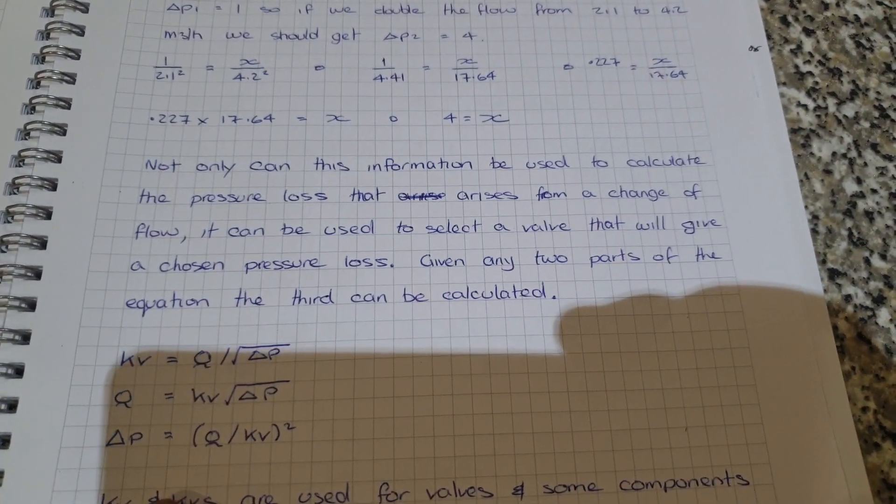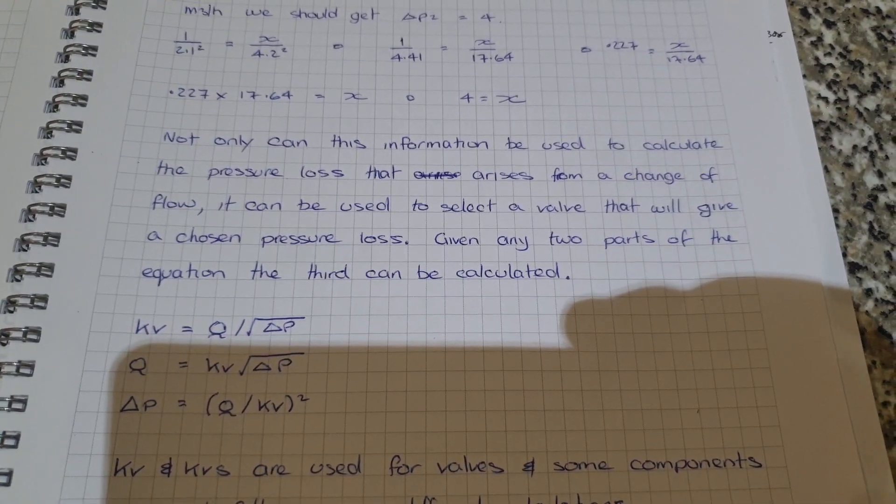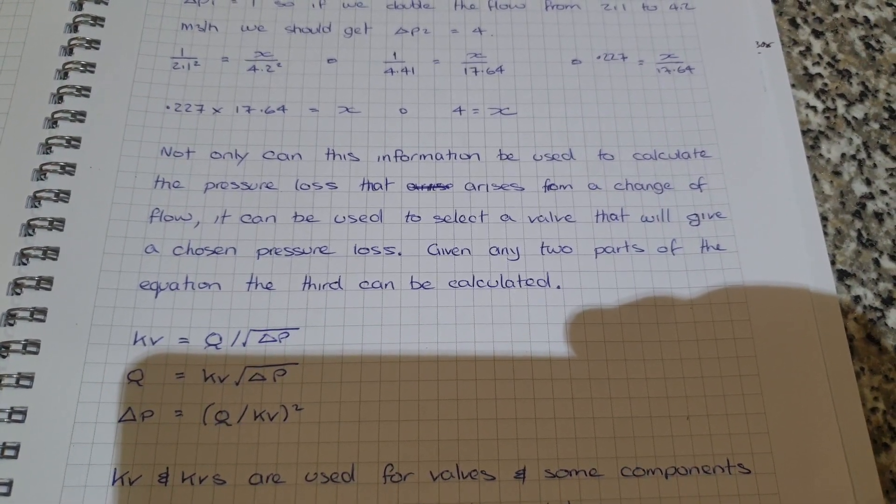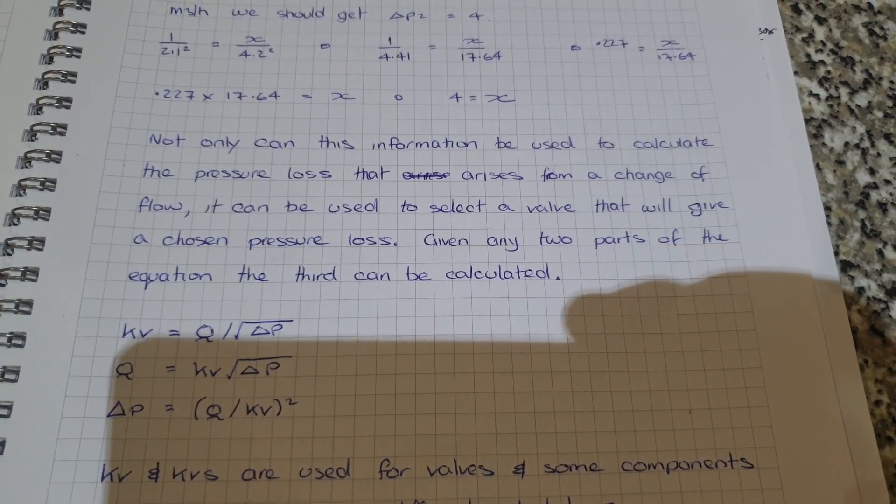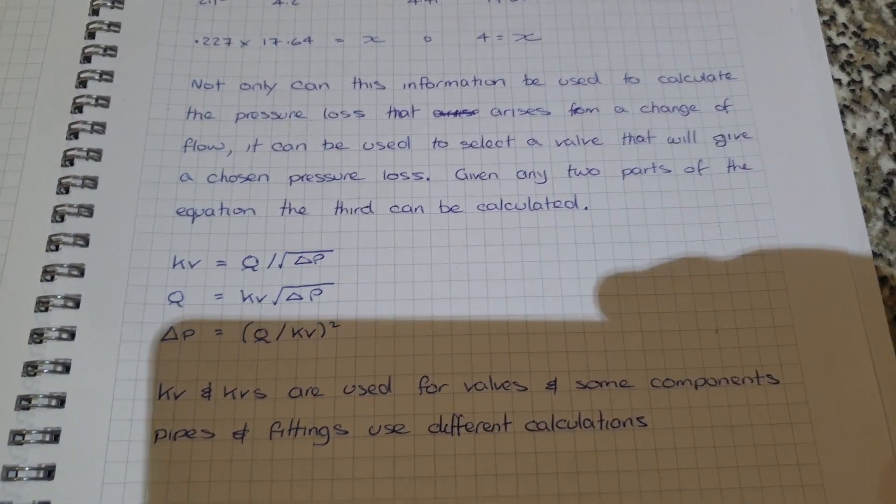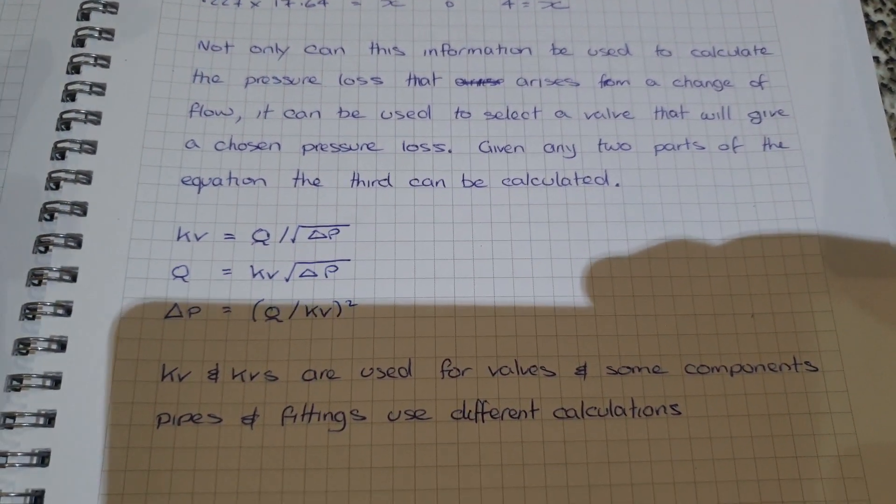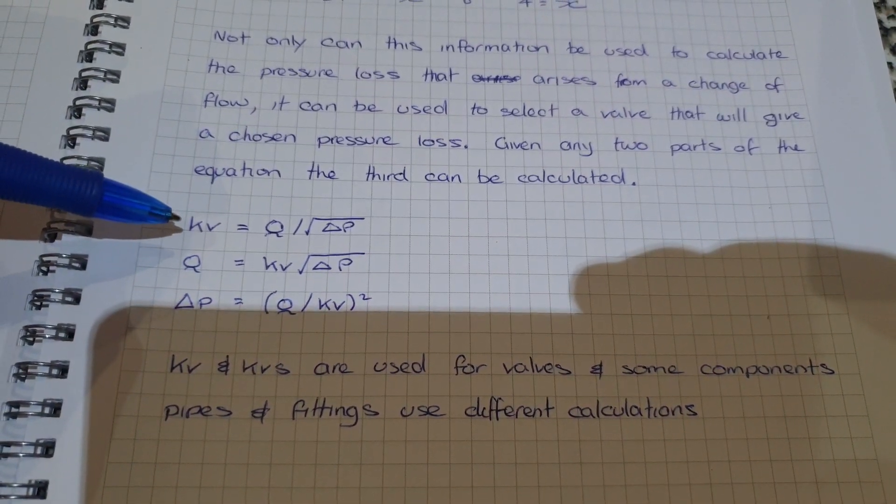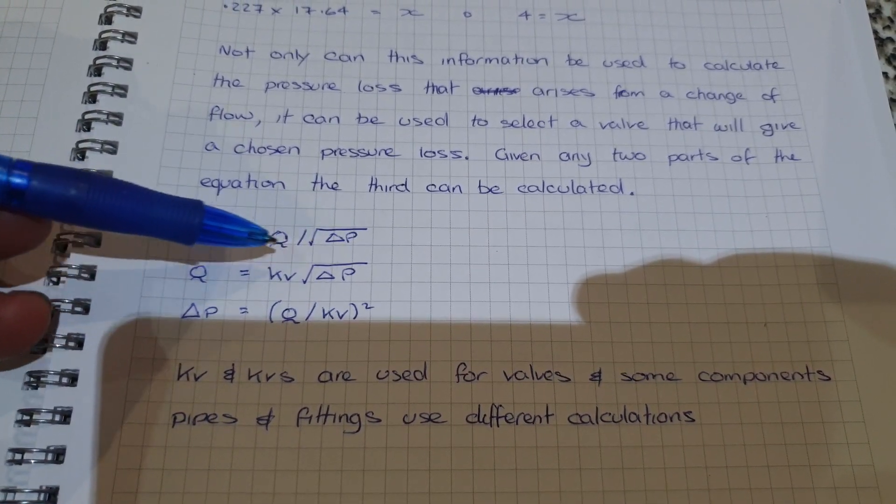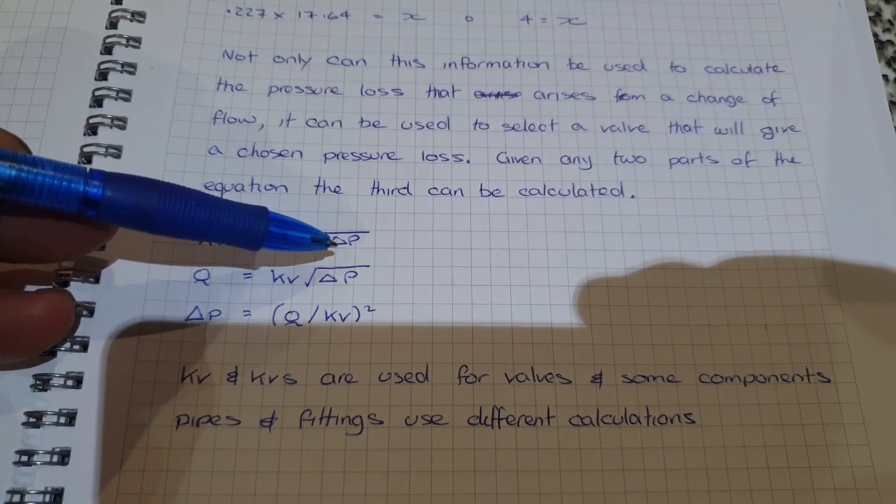Now, not only can we use this information to calculate the pressure loss that arises from a change of flow, it can be used to select a valve that will give a chosen pressure loss. Given any two parts of the equation, the third can be calculated, and through transposition we end up with three useful formulas. If we want to know the KV value of a valve that we want to buy, if we know our flow rate and the delta P that we want, Q divided by the square root of the pressure drop we're after will give us the KV value.